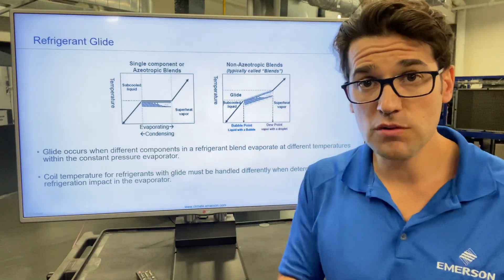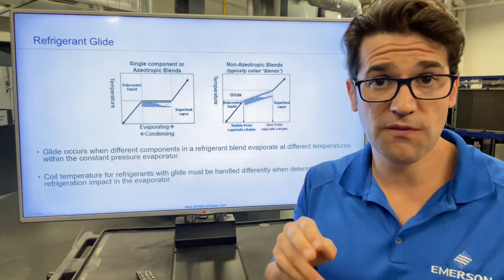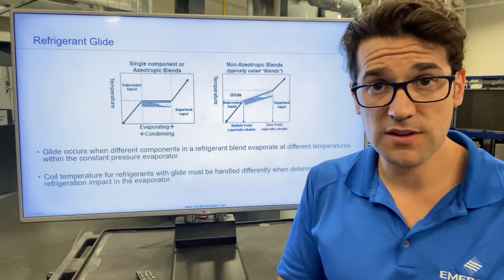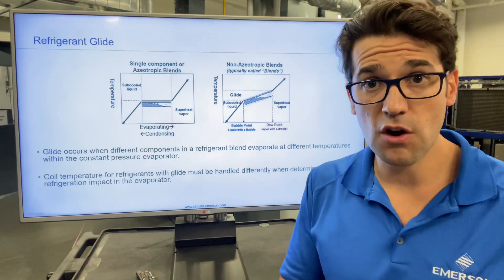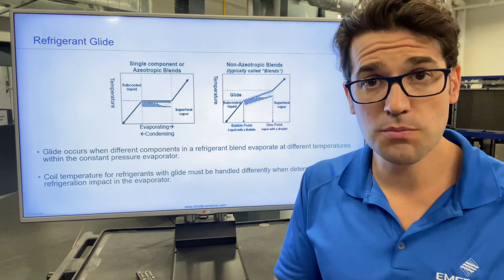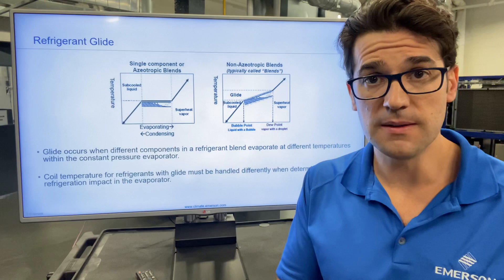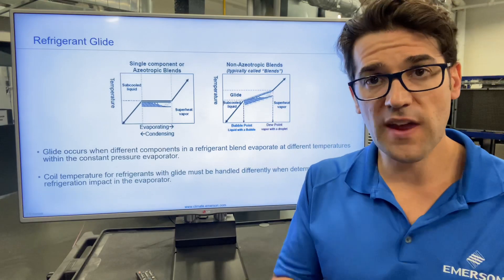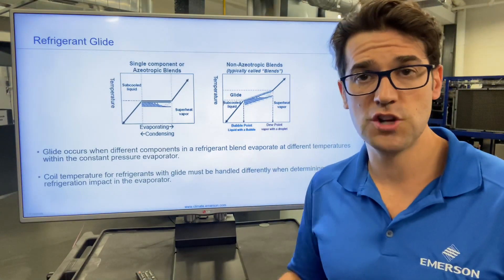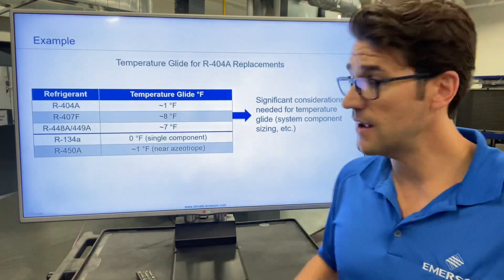Because if you don't and you use the bubble point, you could flood back that compressor and have no superheat, or you have way too much superheat and cause overheating. So it's very important to use the dew point when you're checking superheat because of this.